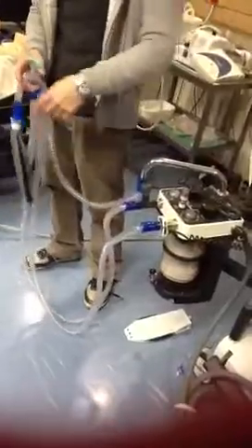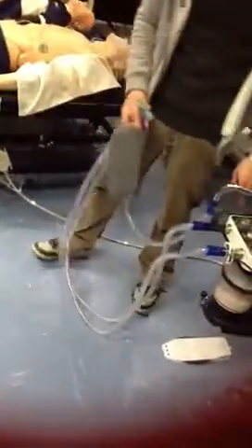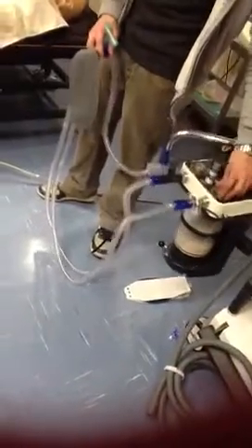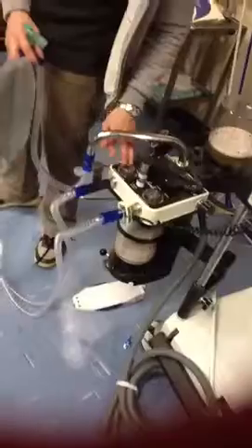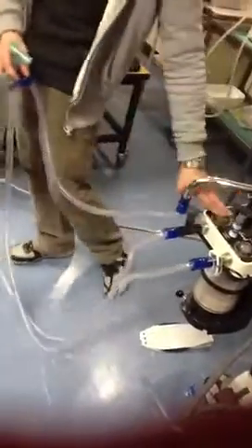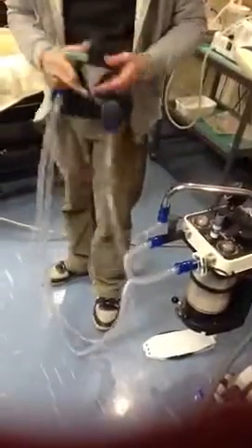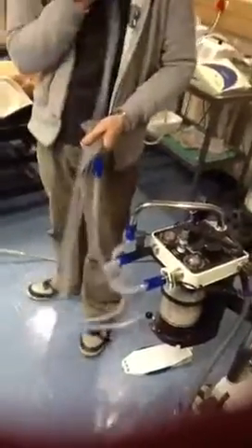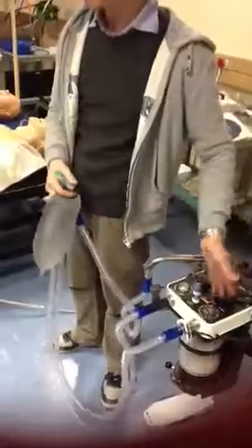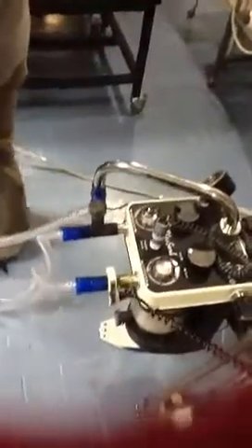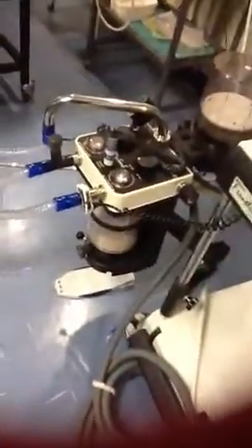Alright. The other thing that you have to test on your circle system: the circle system is dependent on unidirectional flow. Okay, and to get unidirectional flow, you have to have valves that are working properly. So you have to see that the valves are moving, because sometimes they get stuck. If they get wet, they get stuck, and then they can obstruct the flow. So for the expiratory valve, you basically just want to blow into the pipe and see that the valve is hopping up and down. Okay, and for the inspiratory one, you'll basically just squeeze your bag to see if the inspiratory one pops. So just squeezing for the inspiratory one and blowing for the expiratory one.